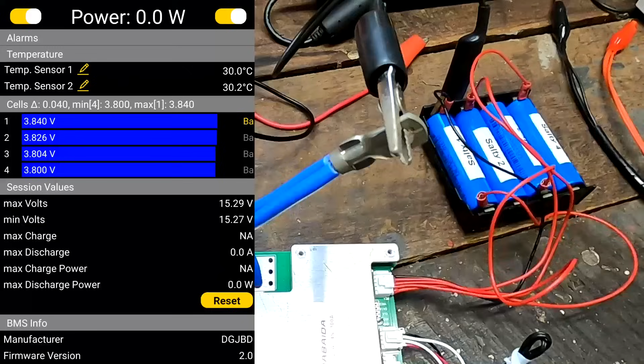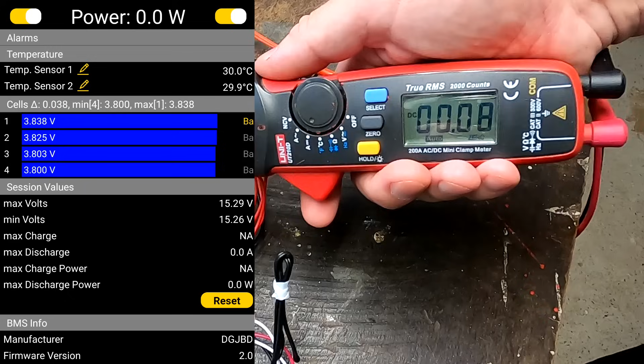So we are balancing with 60, 40, 60, 70, I would say around 50 milliamps. Balance current 70 milliamps, that's not too bad actually for a passive balancer. Twice as much as the Daly. And this should be a sufficient balance current for this sodium battery here.